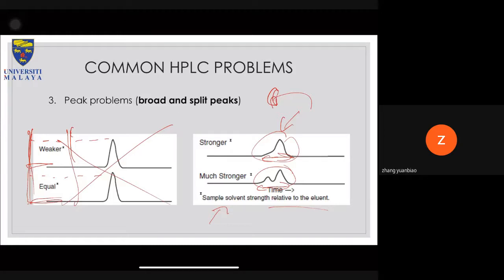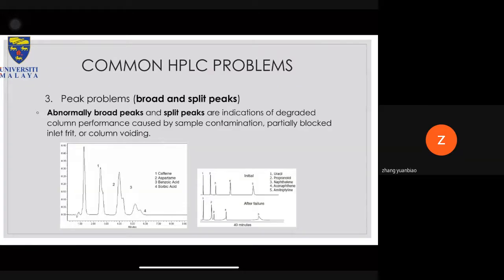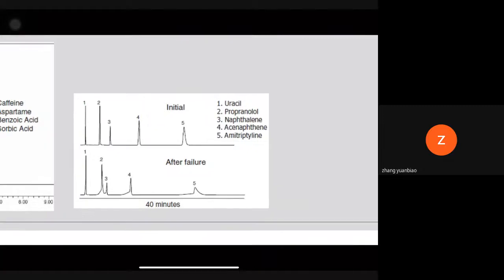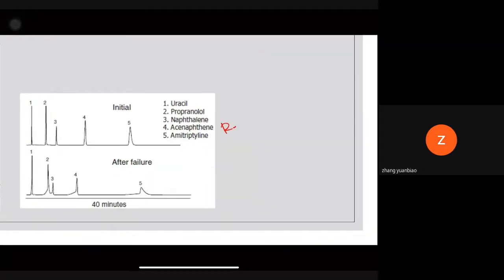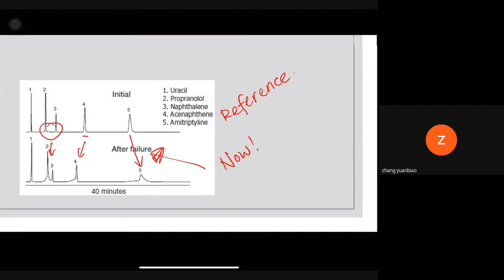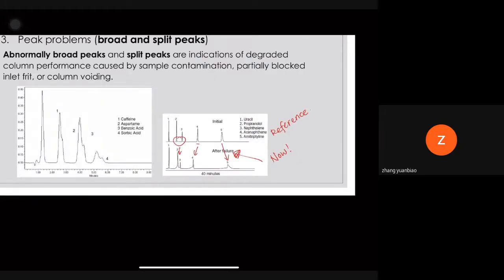So broad and split peaks, abnormally broad peaks or split peaks, are an indication of degraded column performance caused by sample contamination, a partially blocked inlet frit, and column voiding. So this is an example where initially that is your reference, and this is now, or after failure. So if initially all the peaks look symmetrical enough, there are no tailing or overlapping peaks, then you do know that something is wrong with the column, especially because there's a huge drift between some of your peaks. Then you know that, okay, this is as a result of the column.